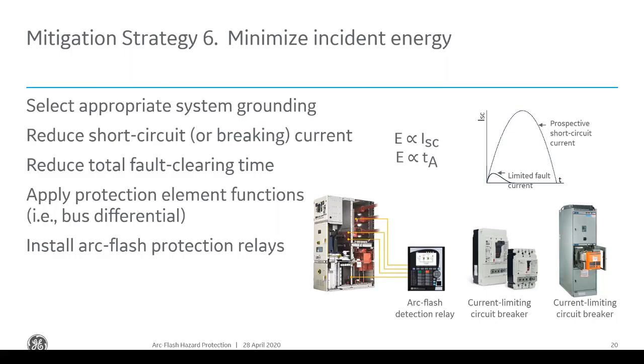Reduce the short circuit or breaking current. One of the most effective techniques: energy is directly proportional to fault current, as we saw in the previous equation, and it's also proportional to tripping and arcing time. So if we can reduce either of those two, that will significantly reduce our released energy or incident energy. Grounding is a vast topic, so maybe we can send a poll out to see if you are interested in a seminar just on system grounding. It's very important, but it's not something we're going to talk about today. Just know that proper system grounding is also a mitigation technique.